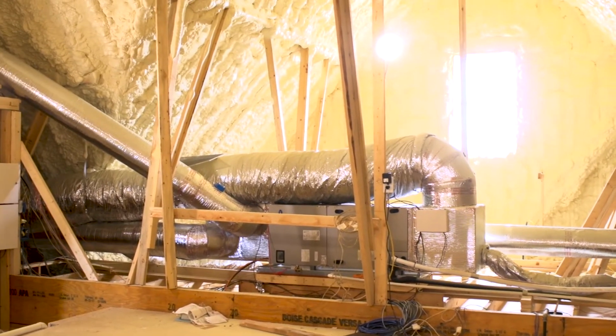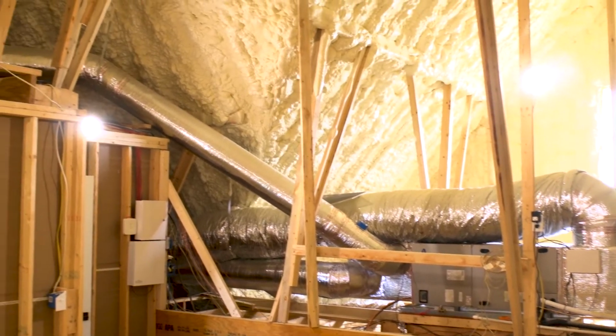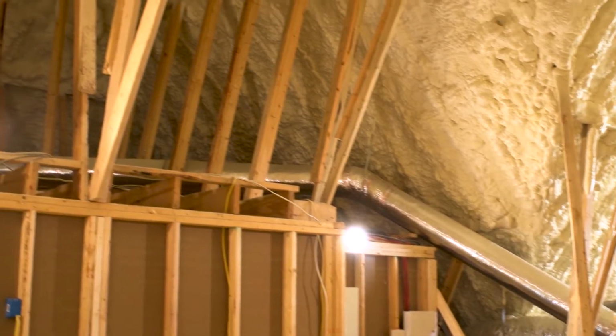The biggest thing that blows my mind is how, when we get these Manual J reports back from a spray foam house, it's cutting the tonnage almost in half, easily. That's really amazing, considering this house we're in today is 4,200 square feet, and it's one 5-ton unit on the whole house. That's a neat point to drive home, that the efficiency level of locating it inside that thermal envelope is such a big difference.